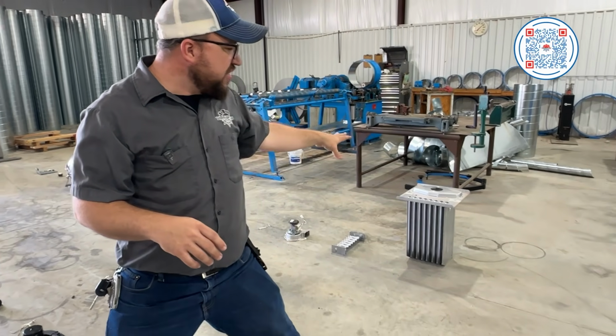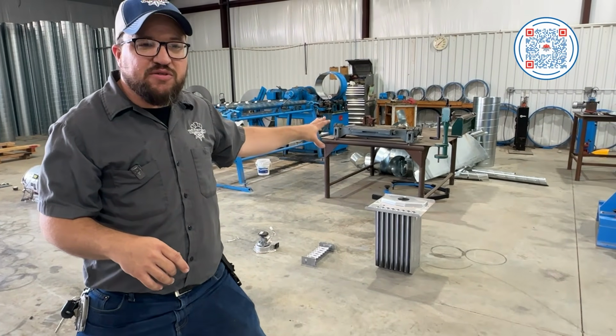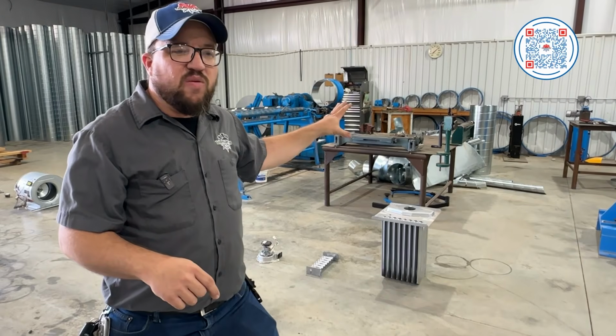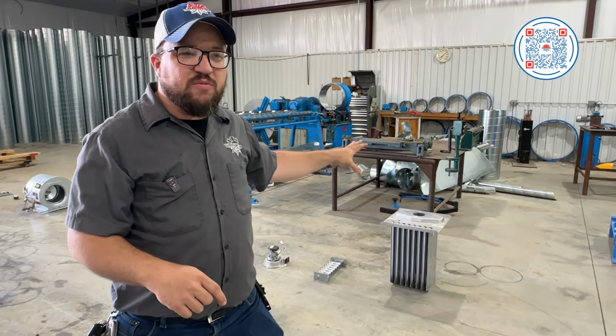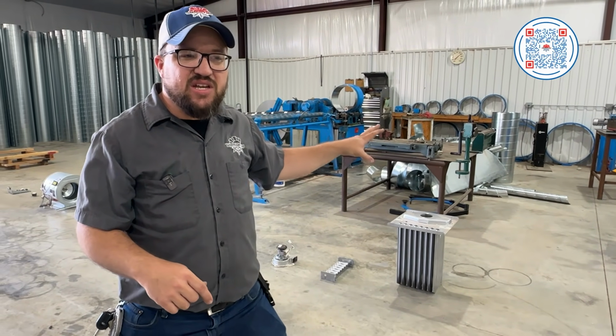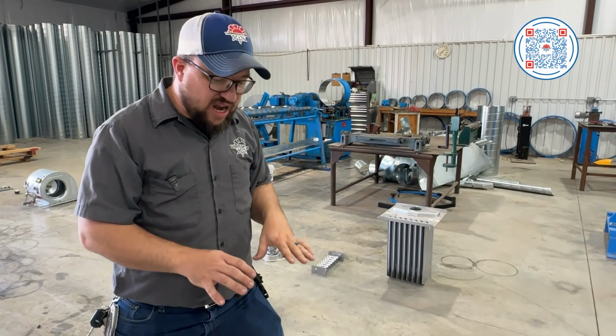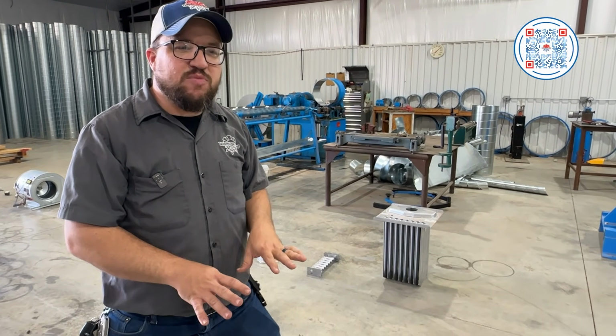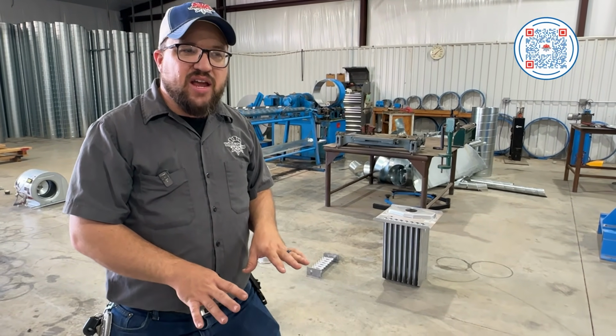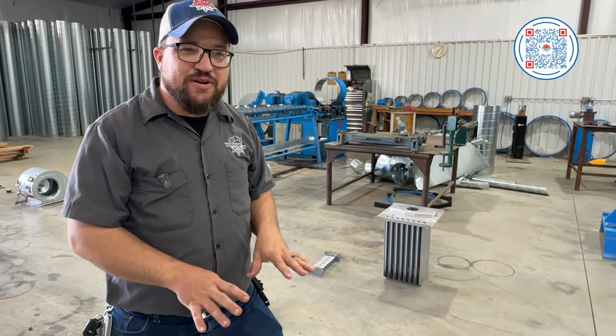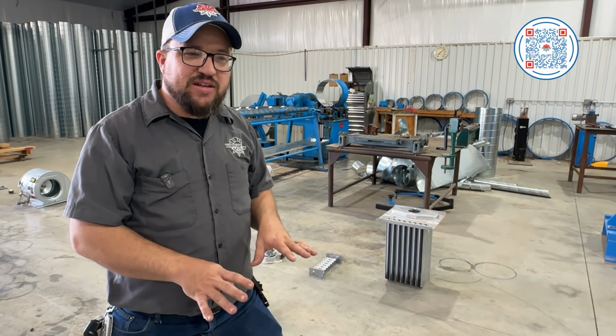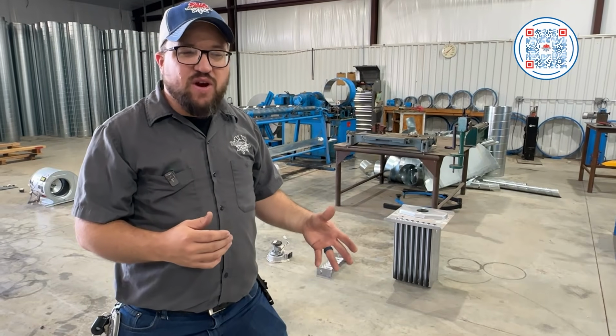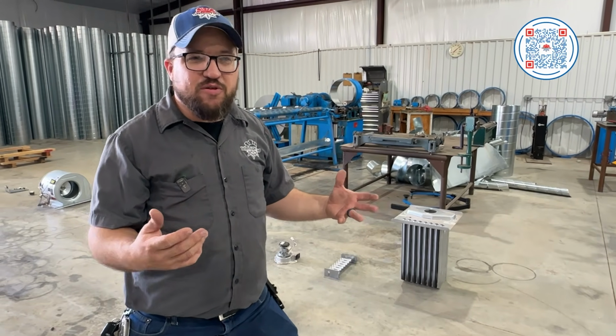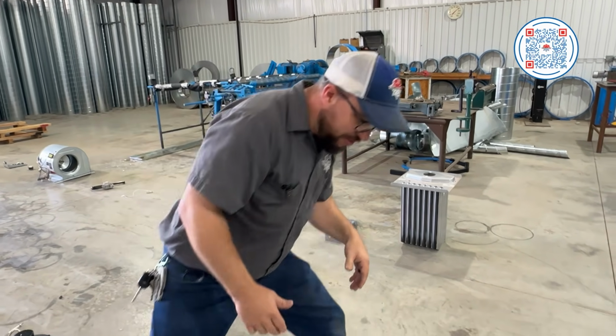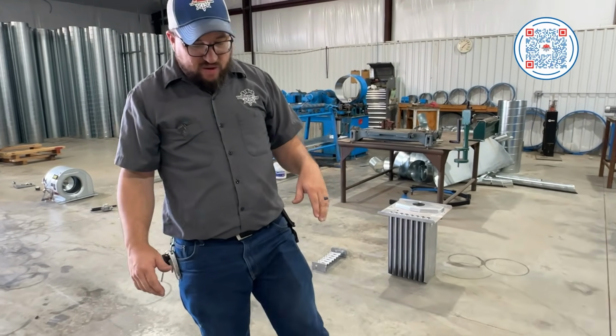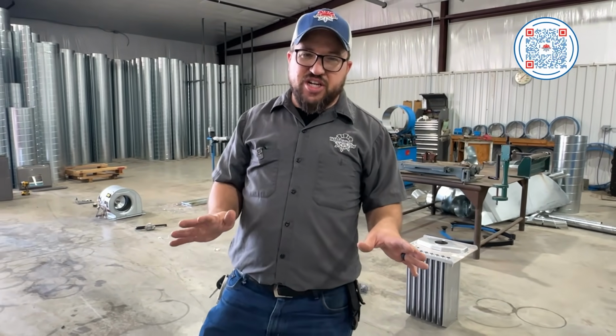With an 80%er furnace, one thing it doesn't do is condensate. With condensate, we've been dealing with it for years and we have all the protections. The problem with a 90% furnace is it only has a problem about one week out of the year, but that week is the coldest week, because we get situations where drain lines freeze up from sending water through somewhere really cold. That's why we don't suggest putting them in the attic.